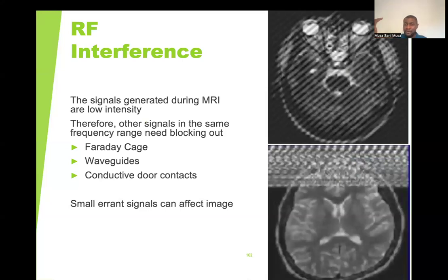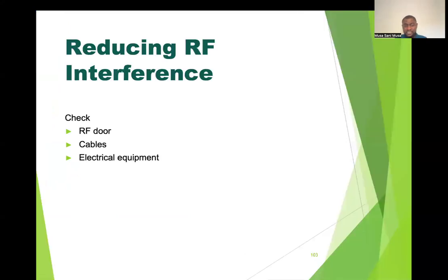Because you've got RF, and there's RF interference, or the Faraday cage, or you've left the scan room door open. So any small stray signals can affect your image. What can you do to fix this? Just check your doors, make sure your door is locked properly, check cables or any electrical equipment, and then boom, problem solved.